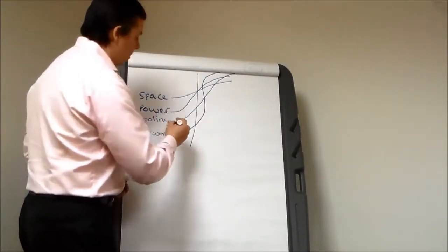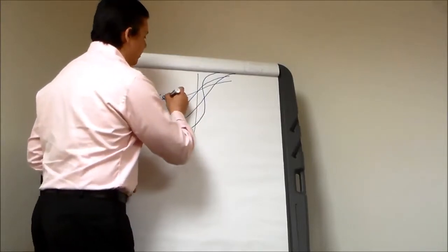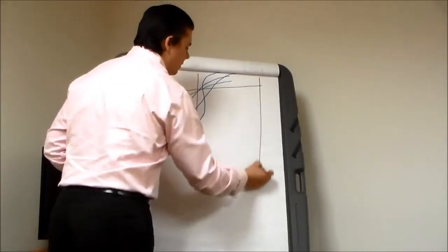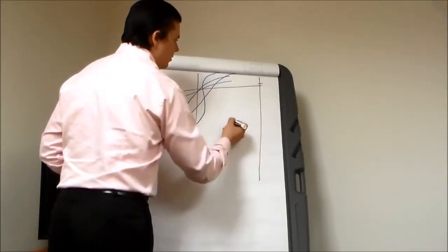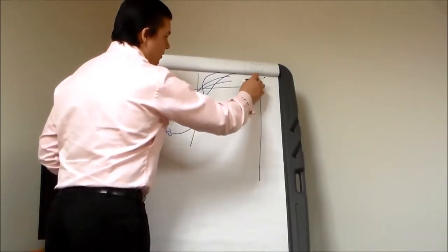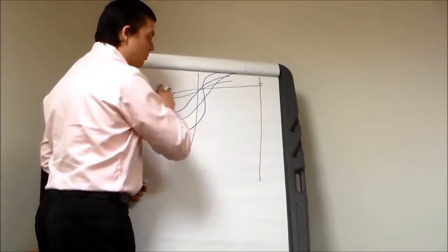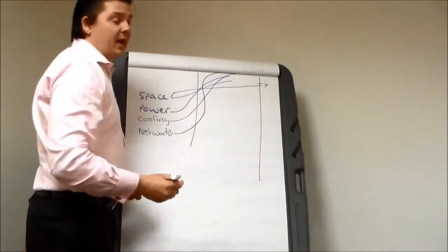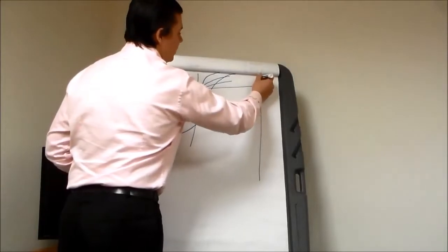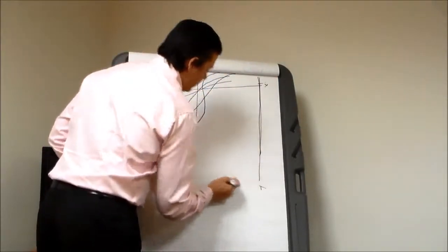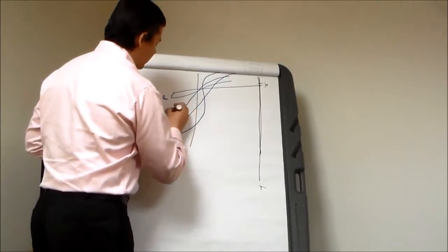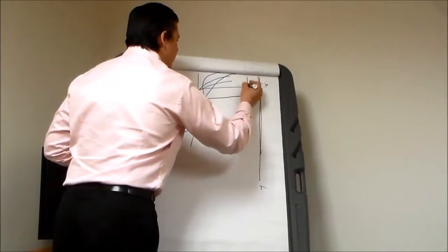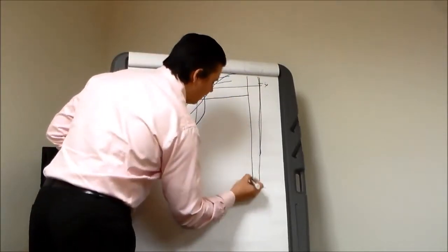The other way of doing capacity management is to draw lines off of these. So you can go, well, line, office space, if we go like that, at this point in time we can only get this much space, and we're using this amount of space at this trend based on what we've done in the past. We're going to need about X amount of space. And that means we will run out of space at this point in time. I can do exactly the same on power. If I carry on with the power and draw a line off of that, okay, cool. Time on power.